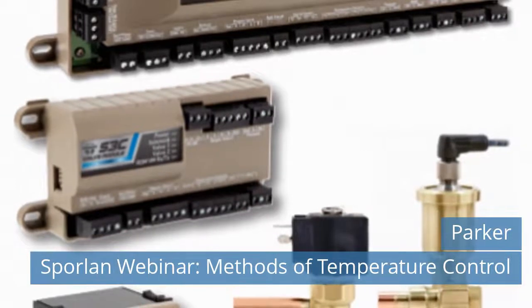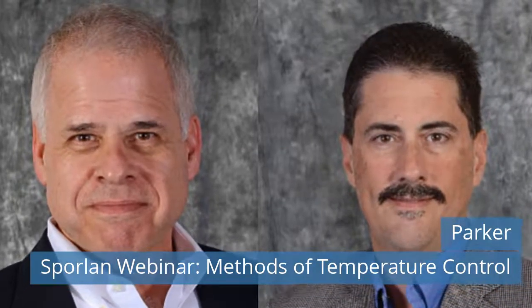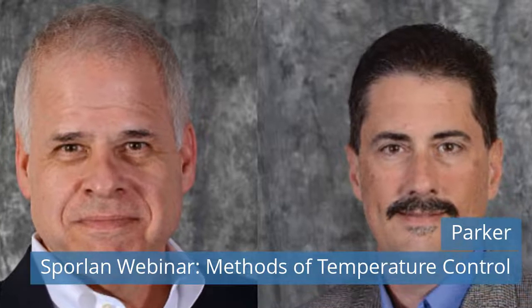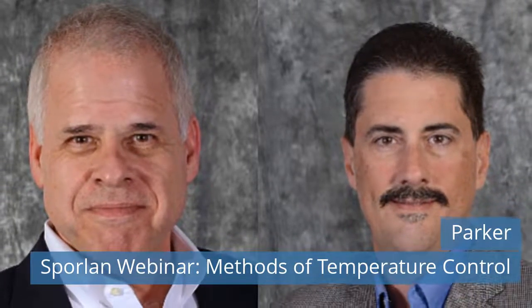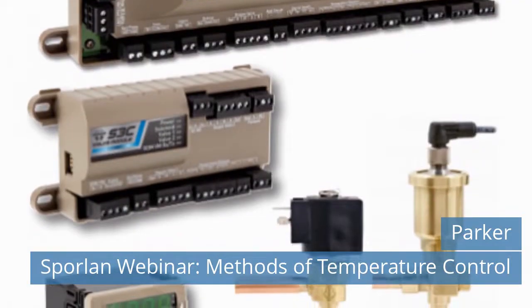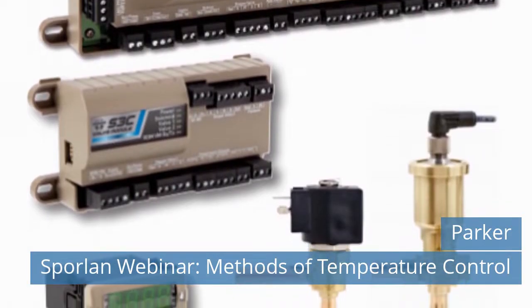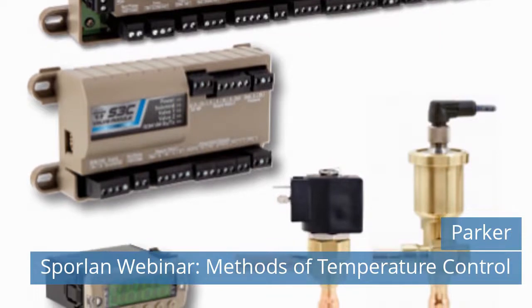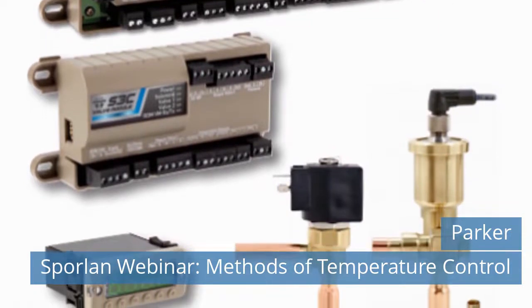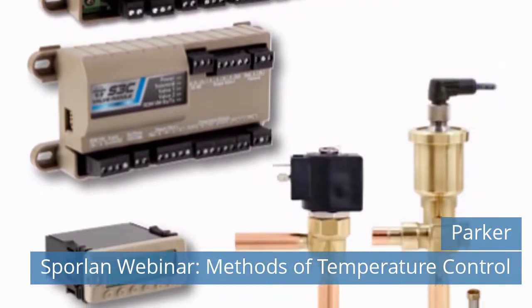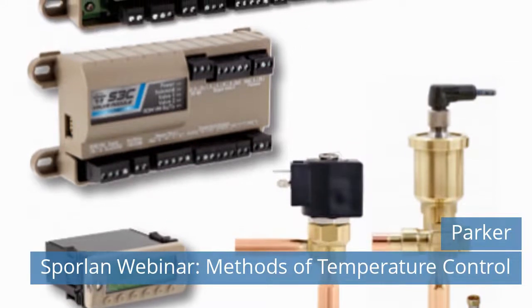Parker Sporlan webinar on methods of temperature control, AEBS and discharge air temperature control. Jim Jansen, senior application engineer, and John Whithouse, senior principal engineer, will discuss methods of temperature control with AEBS controlling discharge air temperature, and how controlling the case temperature and suction line superheat can successfully be done with an electrically actuated, electronically controlled valve, the AEV.